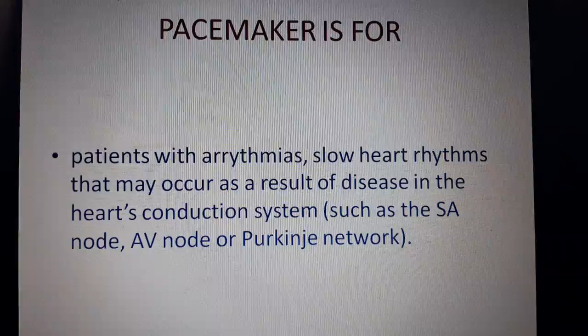the help of a pacemaker. A pacemaker can be of fixed rate, that is, it produces the pulses without considering the condition of the heart. And one is the on-demand pacemaker, in which the pulses are produced according to the condition of the heart. That is, sometimes when the heart functions normally, the on-demand pacemaker is turned off and the battery is saved. Due to the slow heart rhythms, it is the case when the valves' opening and closing is not synchronized.